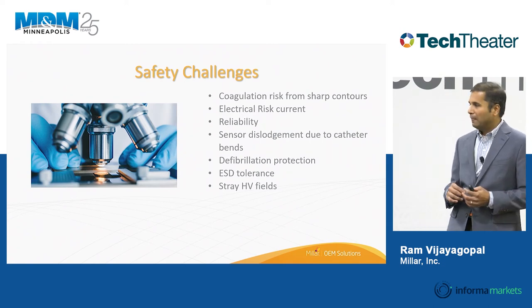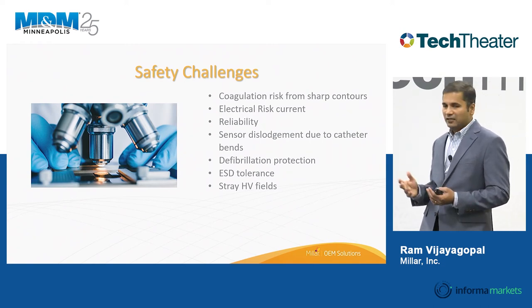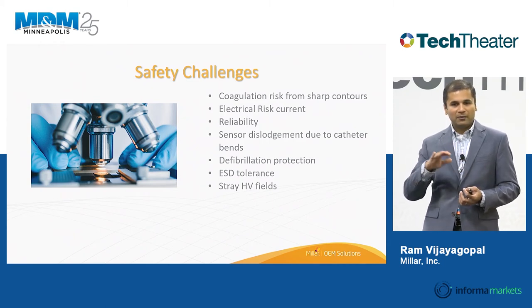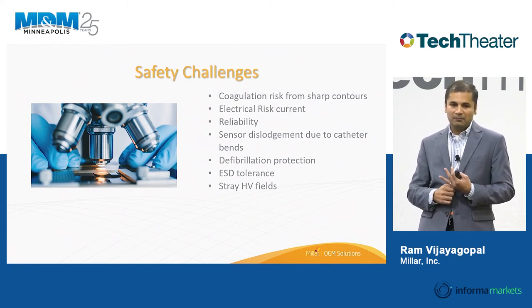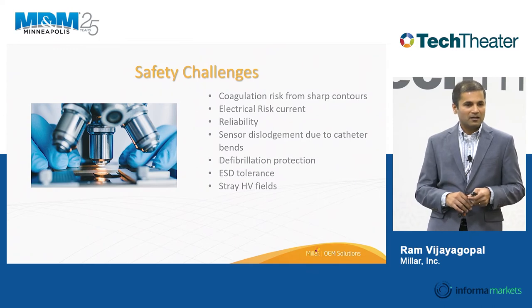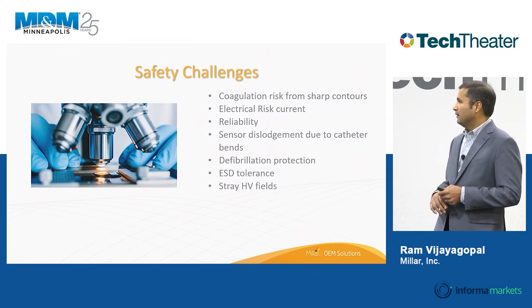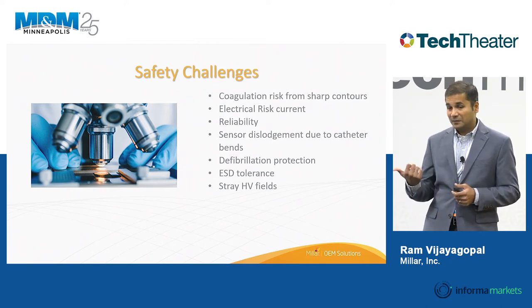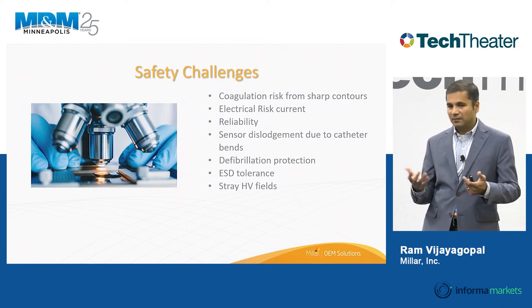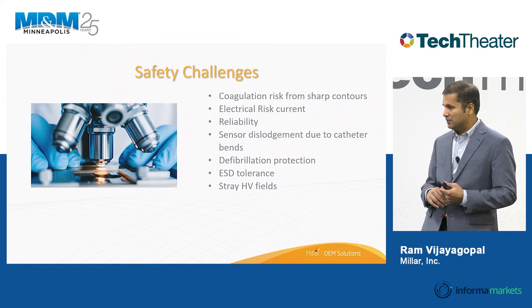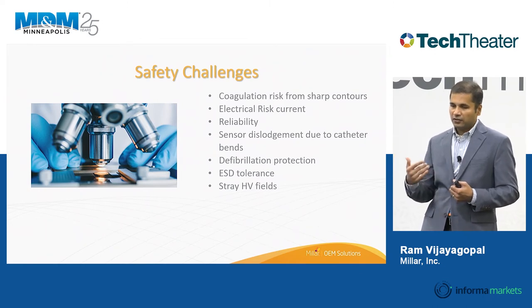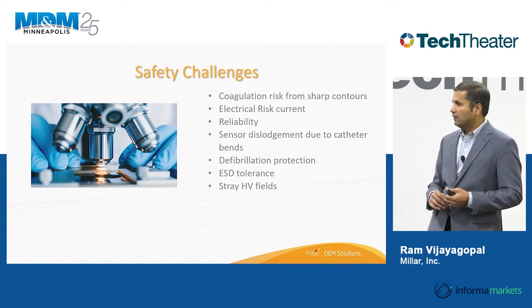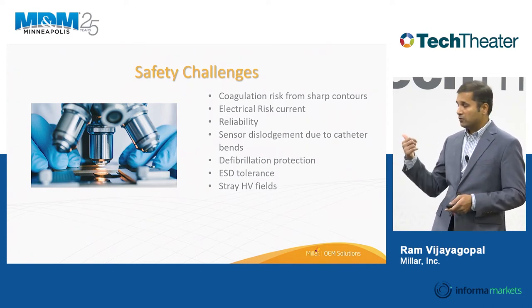Now for safety challenges. If the sensor will be blood-contacting, you want to avoid sharp contours that can cause pooling and risk of thrombosis. You also need to watch out for electrical risk current — most sensors use DC, but if you're using AC excitation, there can be capacitive transfer of current through tissue to earth ground, and there are standards governing this.